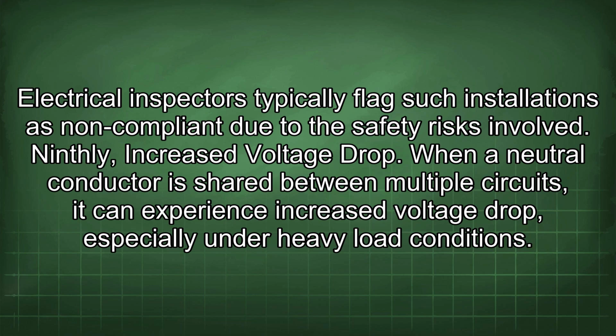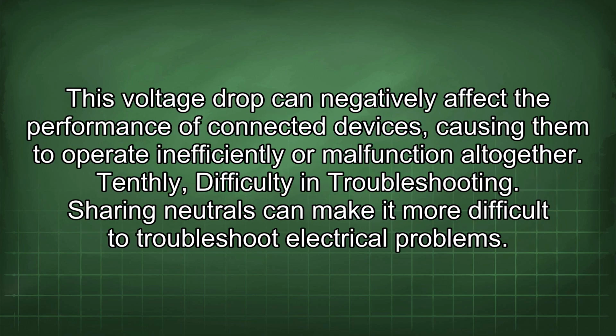Ninthly, increased voltage drop. When a neutral conductor is shared between multiple circuits, it can experience increased voltage drop, especially under heavy load conditions. This voltage drop can negatively affect the performance of connected devices, causing them to operate inefficiently or malfunction altogether. Tenthly, difficulty in troubleshooting.